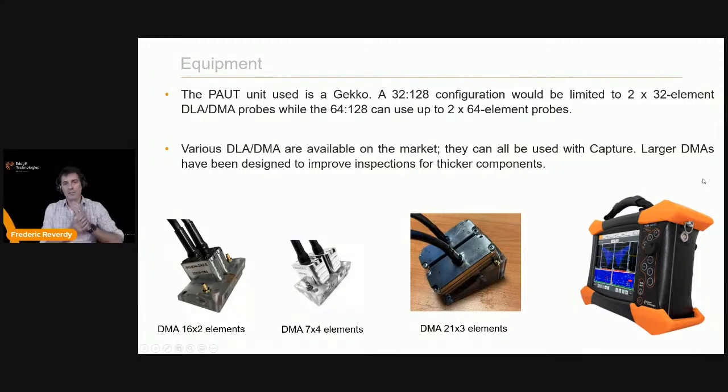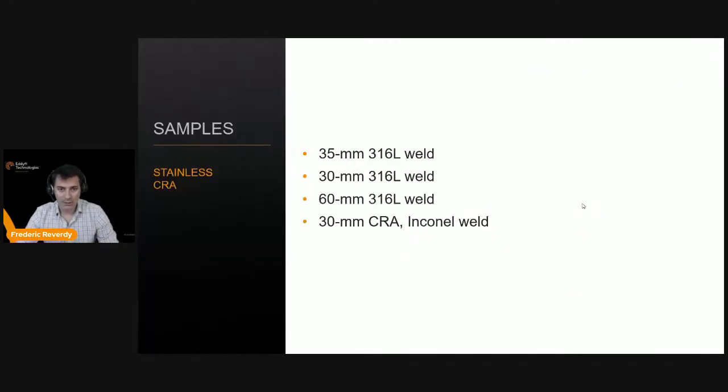The Gekko unit used today comes in 32/128 or 64/128 configurations, with or without TFM. A 32/128 covers most available probes on the market, limited to 32×32. The 64/128 allows bigger probes like 16×2 or 7×4, enabling deeper inspection with larger aperture. You can also use the Mantis — the smaller sibling of the Gekko — as a 16/64 unit limited to 2×16 elements, suitable for small stainless steel tubes with a DLA at a more cost-effective price point.